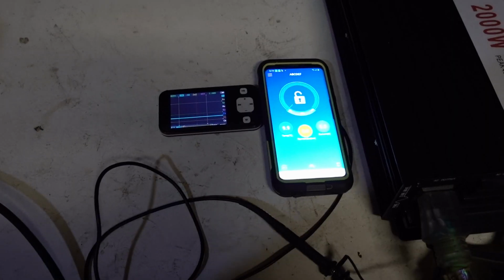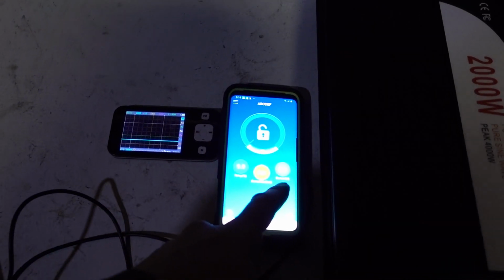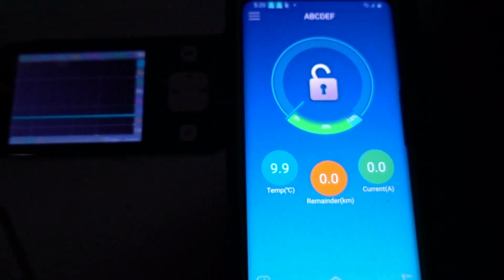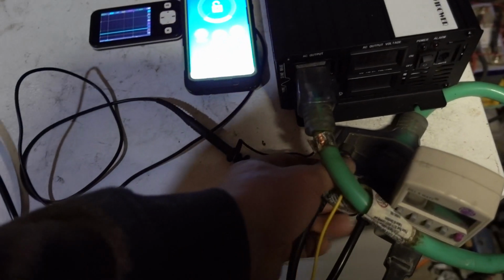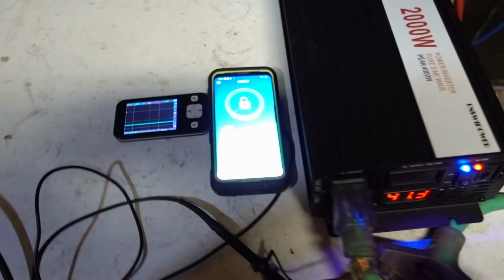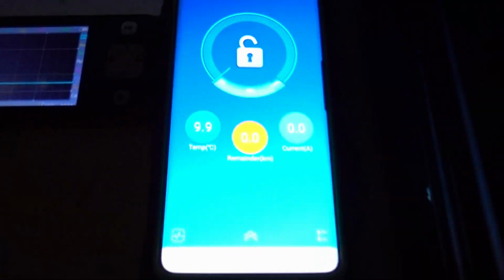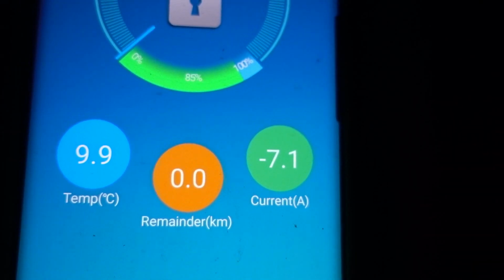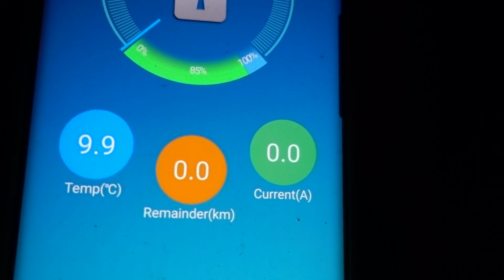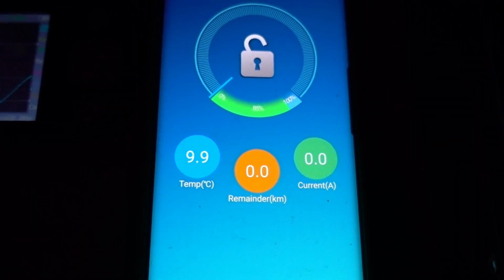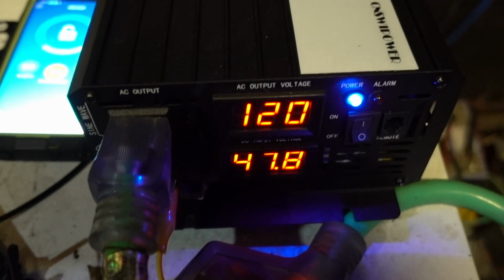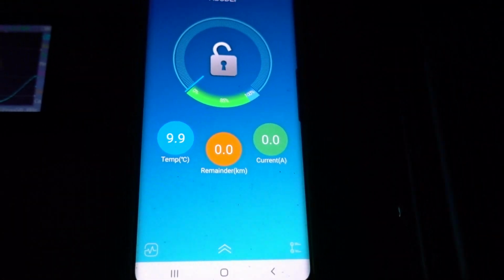I gotta do some calculations and see how much power it was putting out. Okay, so doing the math, it was running 2340 watts on the DC side, but there are losses in the inverter, so I want to see what the no current draw is. We're going to make sure everything is off. What's our no current draw? Better turn that off. That's weird, you gotta have a current draw, can't be zero. It's so low that let's try turning it off again.